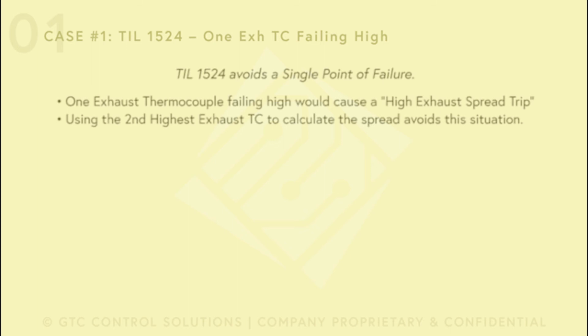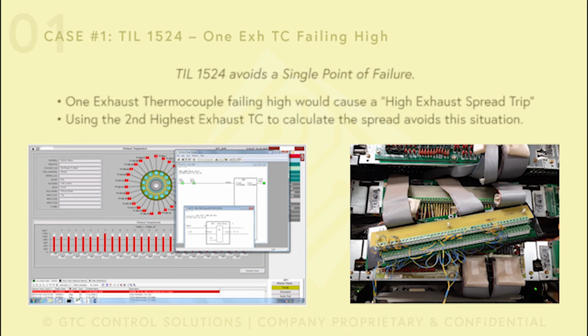The standard software typically uses a simulation that is part of the sequencing, automated simulation, but with all the customers that we discussed this TIL with and implemented the TIL for, they agreed to a very simple modification. We removed the automated testing part of the sequencing because it also affects the startup sequencing. It has a permissive that you're not in testing to allow the startup. And we removed that completely and did a simulation of the sequencing, as I will explain in a couple of minutes. This is how the screen looks after we implemented the TIL.